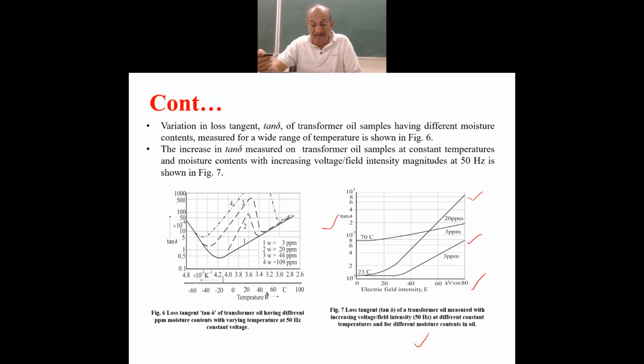Then if you increase the temperature of the oil, this has been measured for oil, you also measure higher values of tan delta at 3 ppm itself.